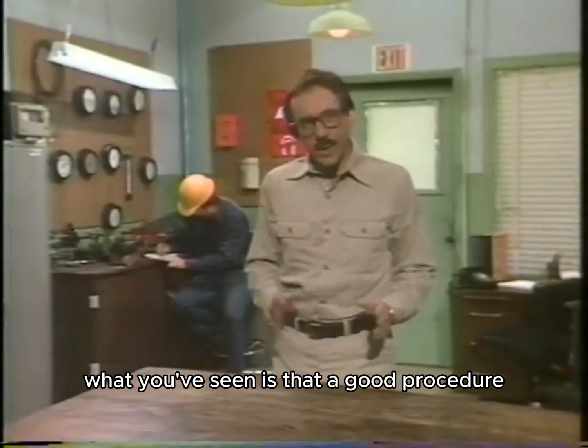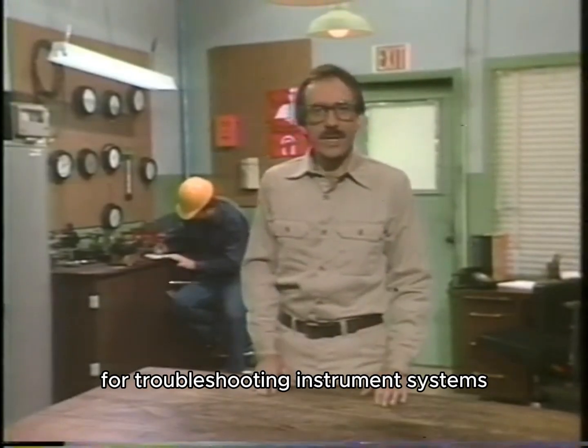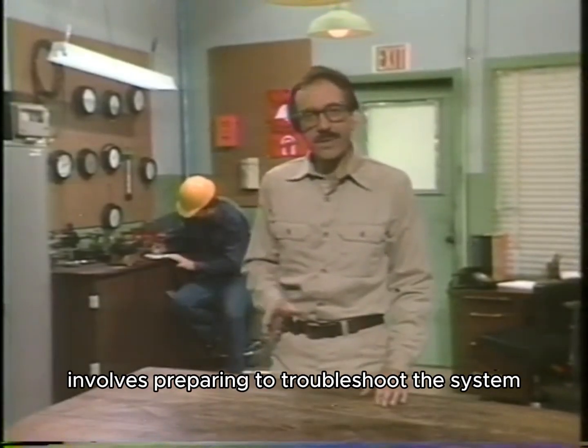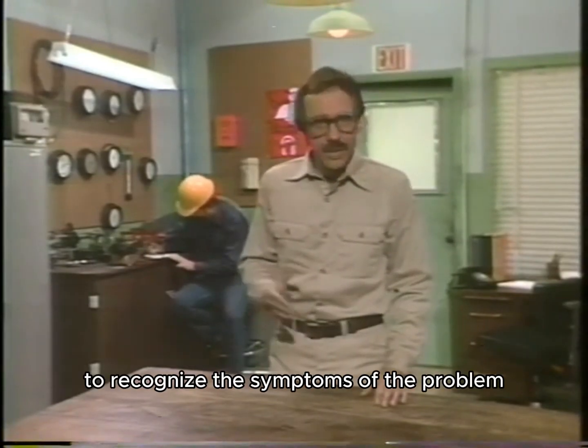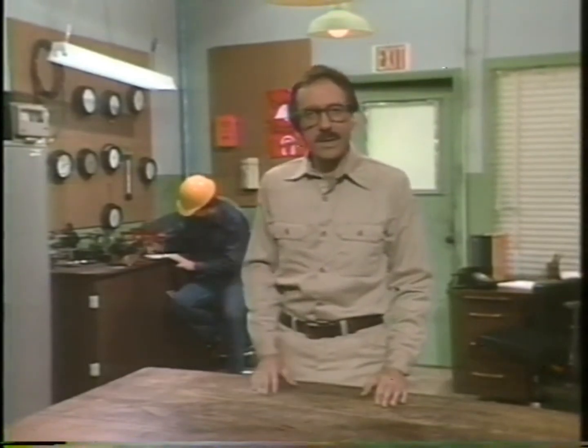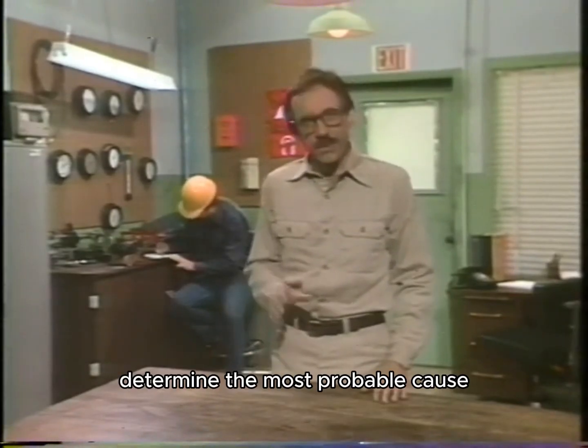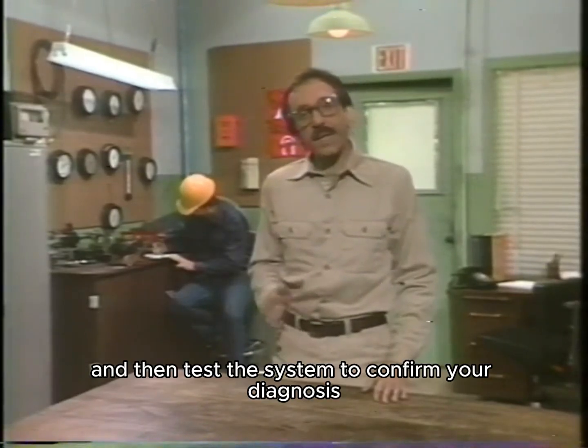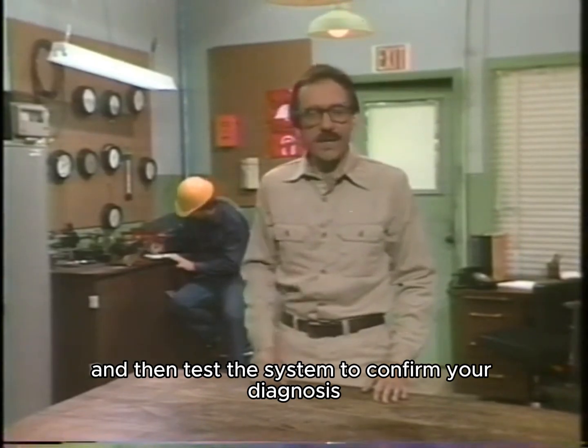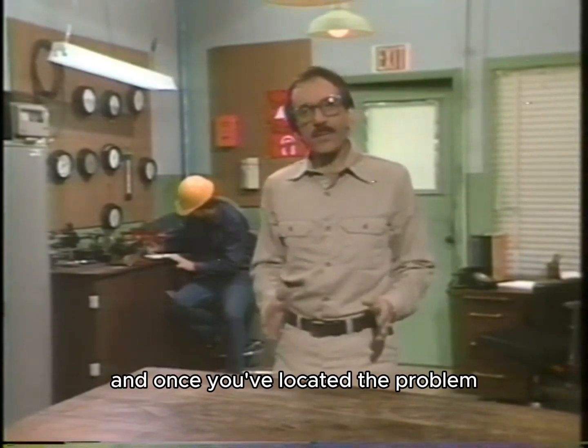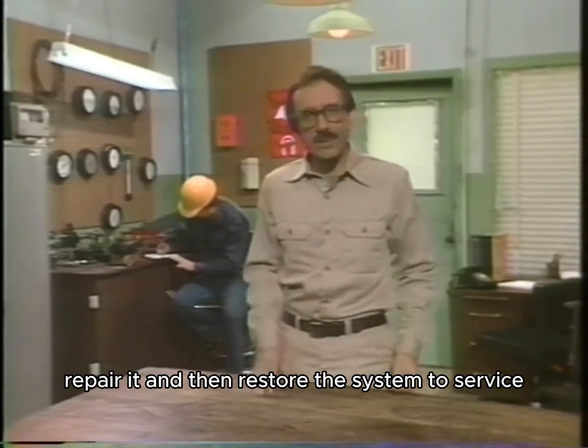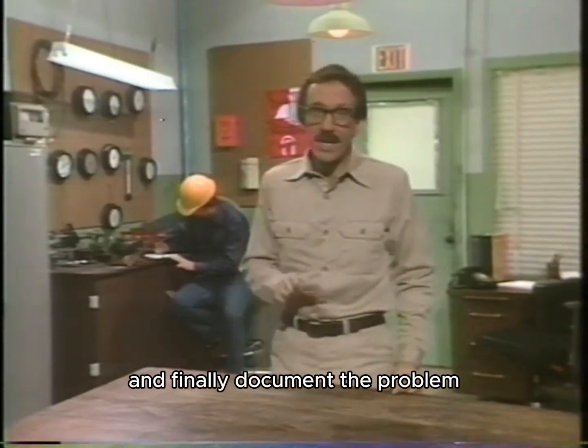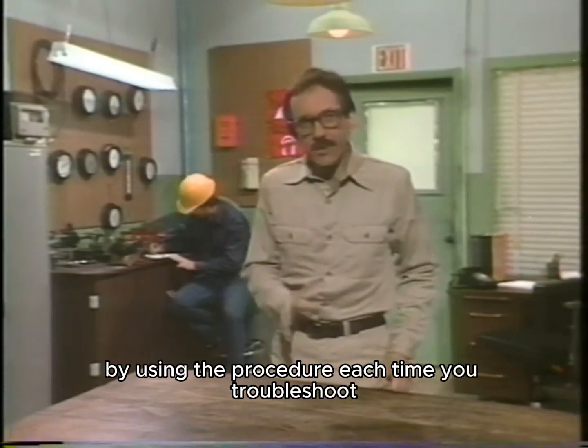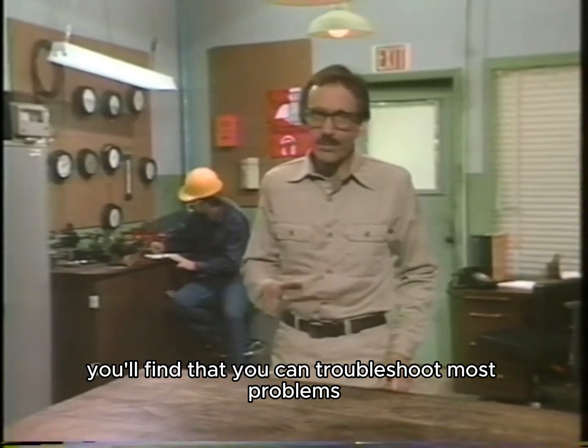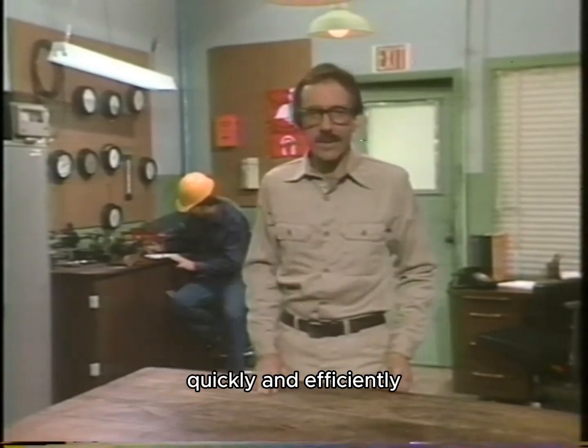What you've seen is that a good procedure for troubleshooting instrument systems involves preparing to troubleshoot the system, then observing the system to recognize the symptoms of the problem. Next, diagnose the problem, determine the most probable cause, and then test the system to confirm your diagnosis. Now, once you've located the problem, repair it, and then restore the system to service. And finally, document the problem. By using the procedure each time you troubleshoot, you'll find that you can troubleshoot most problems quickly and efficiently.